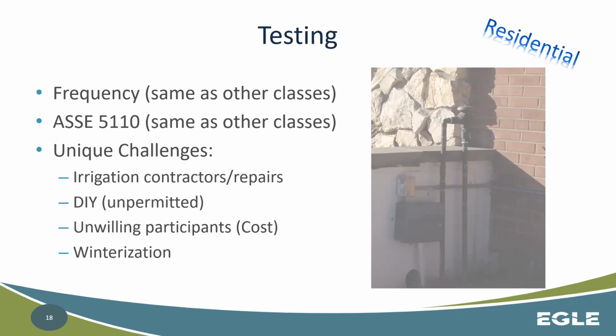Things will freeze up and a pipe will burst. You might get a part of the casing to crack on the actual assembly itself. They can be damaged, and sometimes you can see that externally. Sometimes it might just be the internal mechanisms. A spring gets damaged, something gets bent out of place. That's why testing, for those that you can't see, testing will catch that for you.